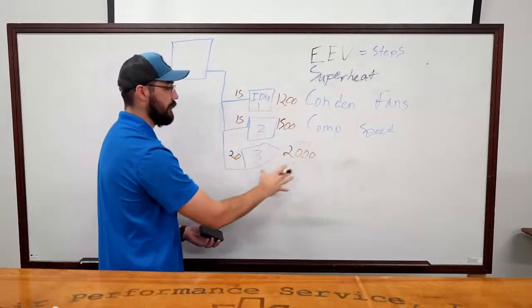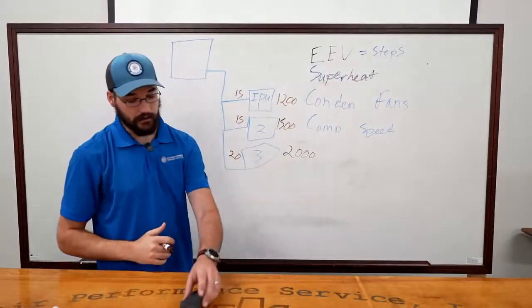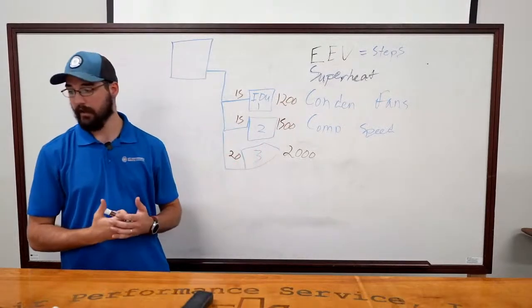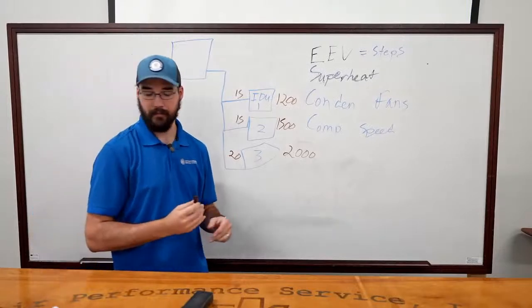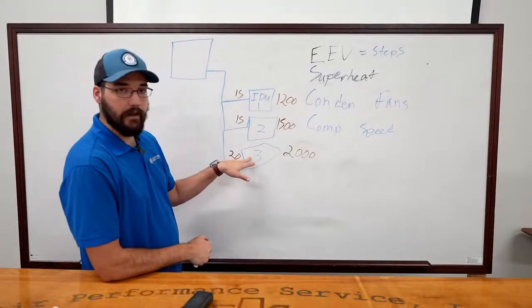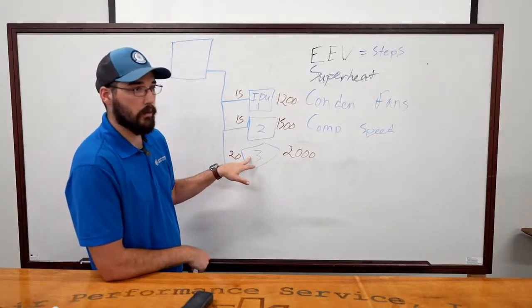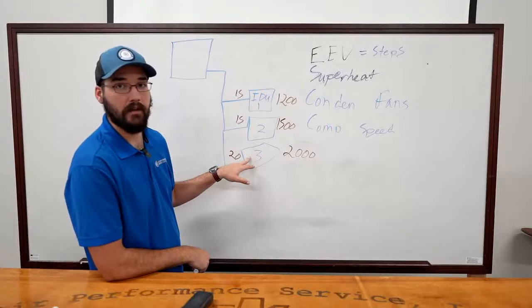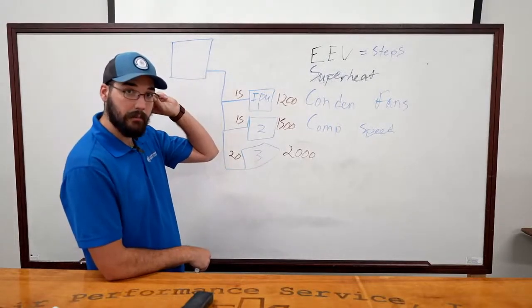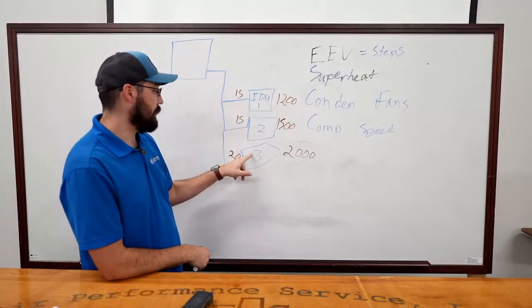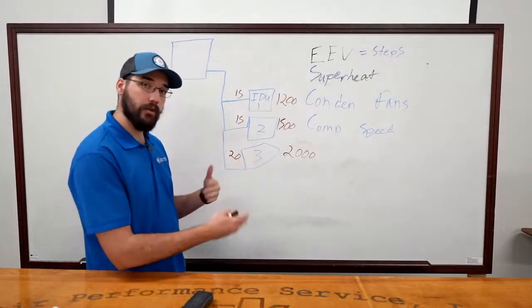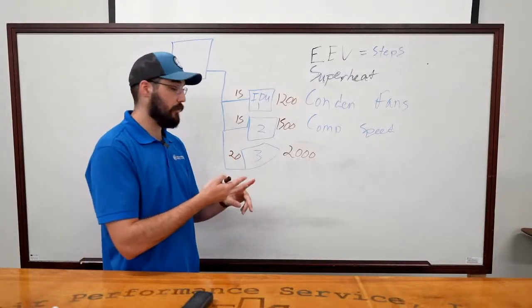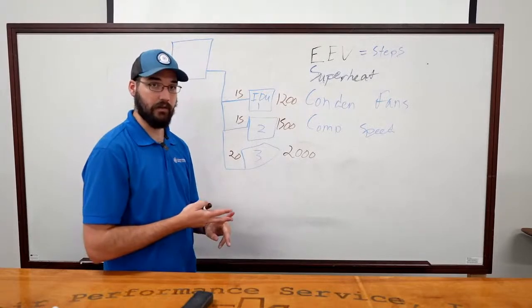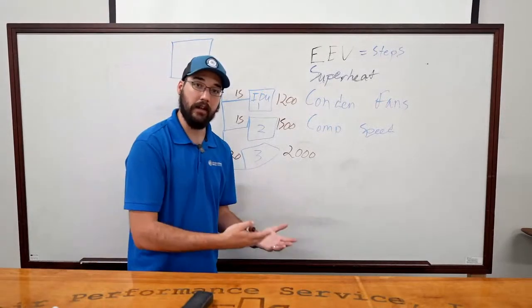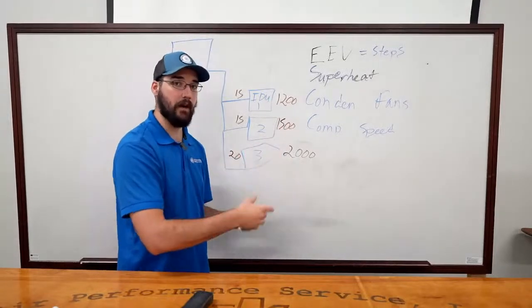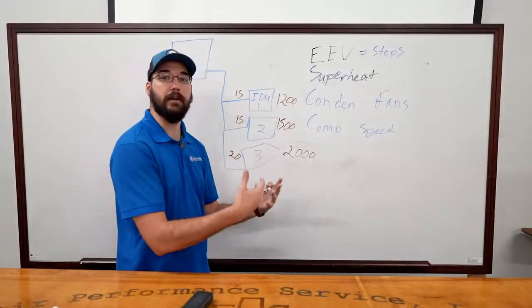So you're going to see this system slowly take off. Honestly, the most common way we find these, if the customer is staying on top of it, is this indoor unit here. They'll just call in: hey, we're warm, we're uncomfortable, why don't you come check it out? The rest of them won't really be complaining because it hasn't hit them yet. So you'll come out to run the service call for this indoor unit, and you'll go through all the checks. There's no alarms, but you're having trouble getting your leaving air temperature to satisfy. The system's just not maintaining. You can cycle power to it, you can do whatever you want, and it's just not keeping up.